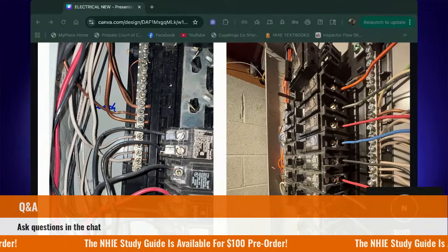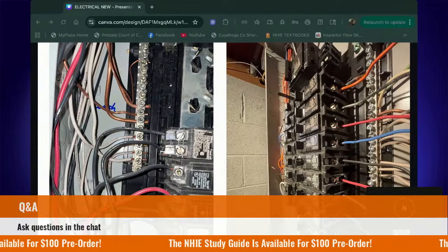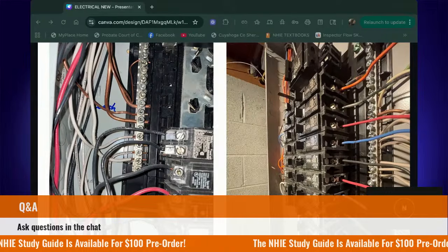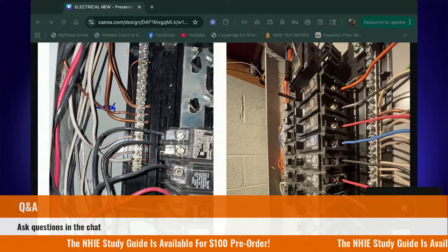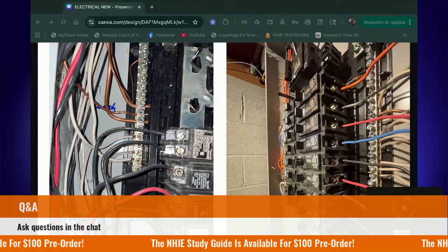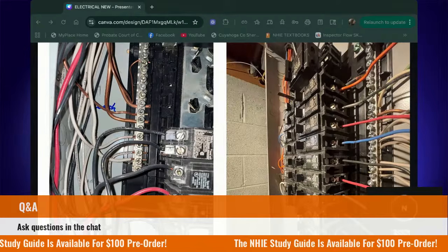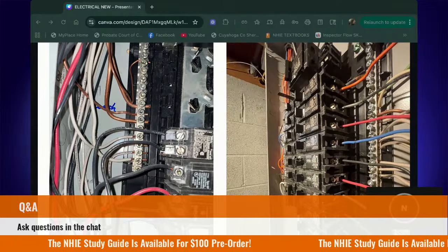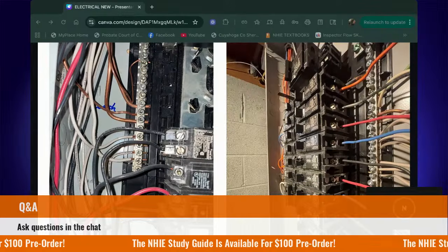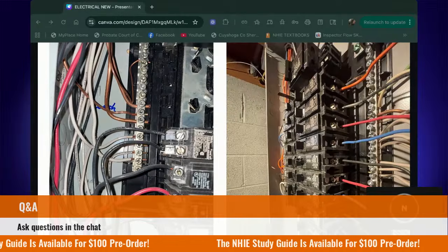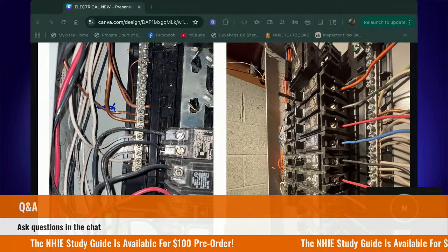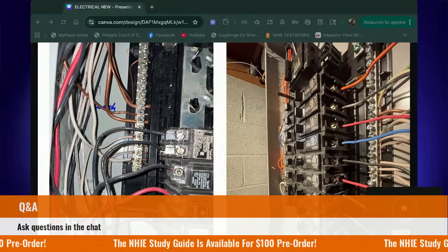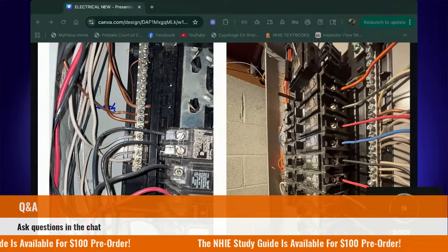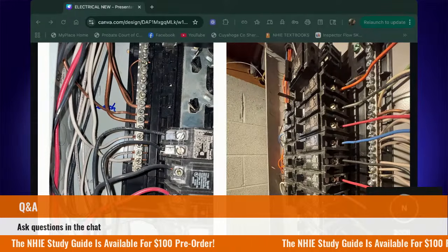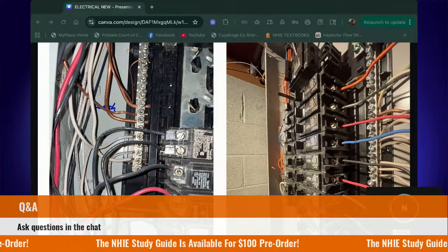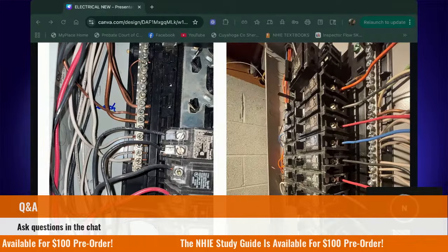Why is the ground wire not carrying current? It's not part of the circuit unless there's a ground fault. I like that. The ground wire is only going to be carrying current when there's a problem. Think about the TPR valve, right? There's never going to be water coming out of the TPR valve unless there's a problem, unless the tank reaches what temperature? 210. Or what pressure? 150. Yes. That would be the only time in a dire situation there would be water coming out of the TPR valve. It's the same thing with our ground system. In normal operation, there should not be any current traveling on the ground system.